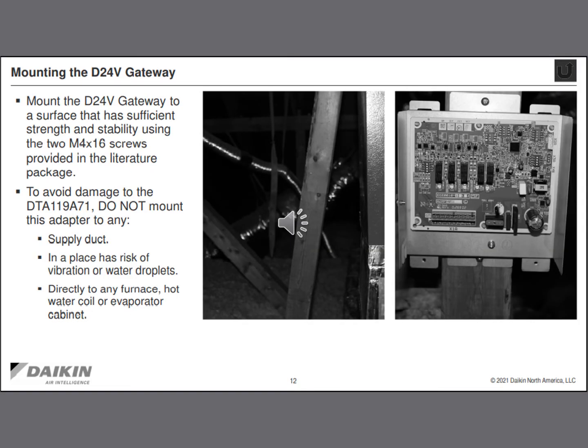So we'll need to mount the D24V Gateway in a secure spot. Daikin's suggestions here are mounting the D24V Gateway to a surface that has sufficient strength and stability using the two 4x16 screws that come with it. To avoid damage, do not mount this adapter to any supply duct, in a place that has risks of vibration or water droplets, and they really don't want you to mount this to any furnace, hot water coil, or evaporator cabinet. So that kind of leaves us in a very narrow list of places we can mount this control.